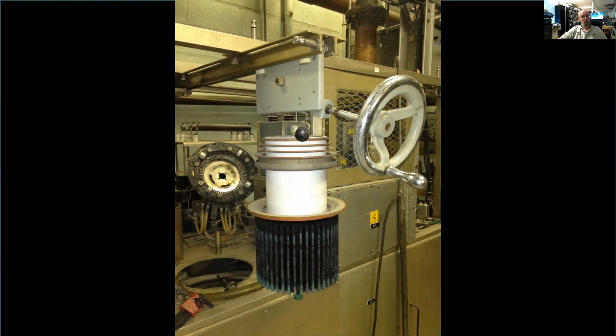Now it's not water cooled, it's actually what they call vapor cooled. It's cooled by steam. It sits in a tub of water, and the water boils off as steam. The steam is carried away to a condenser located up on the second floor, and it returns as water back to the cooling tub to be recycled. It's a continuous cycle.